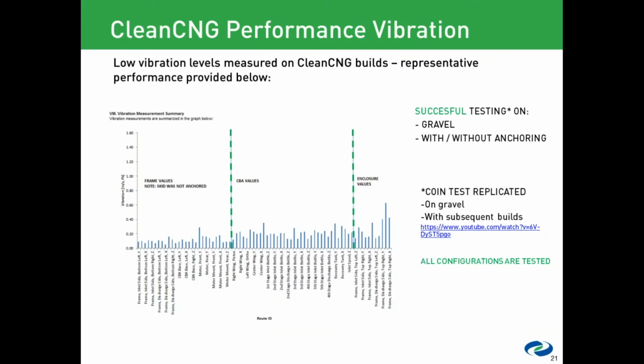The vibration, this is quite a detailed diagram here. I won't pretend to interpret it. I'll let Brad talk to this one. Sure. So this is a plot of some of the vibration levels that we've measured on the compressor that we designed. As a maximum value, in the past we've used 1.2 inches per second as the maximum allowable vibration velocity rate. And as you can see on this plot, every single point of the package that was measured was well below this limit.